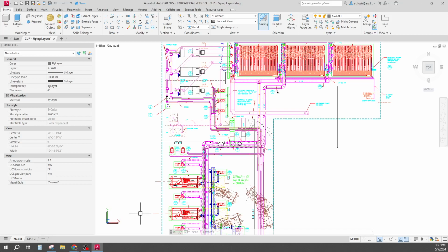So that's two things. And if you were looking at this, I'd say, show me, say this room and this room had supply for the HVAC. Neither room had HVAC return, and the cooling tower room had neither. So those need to get done. Let's take a look at some other things that were not done.